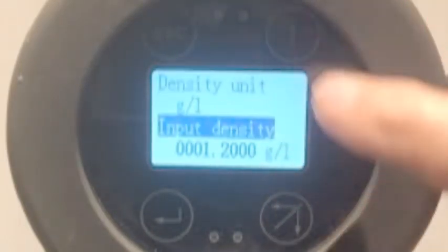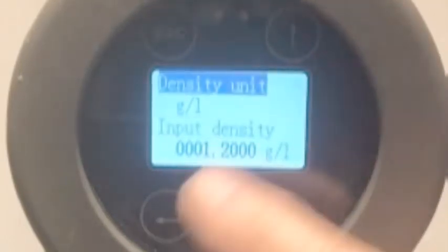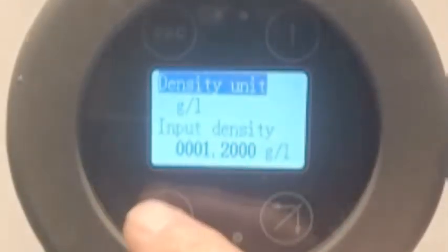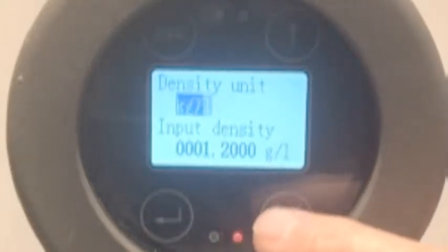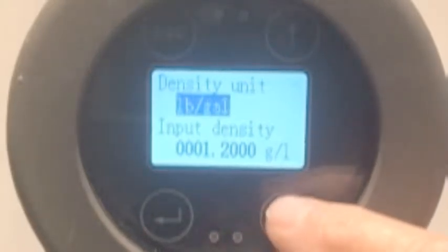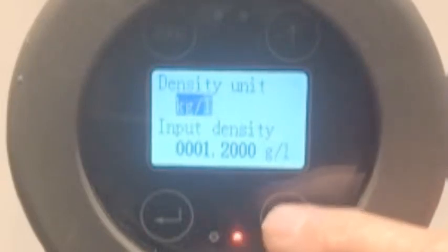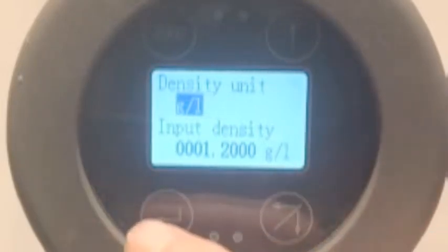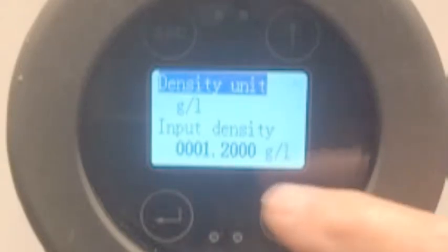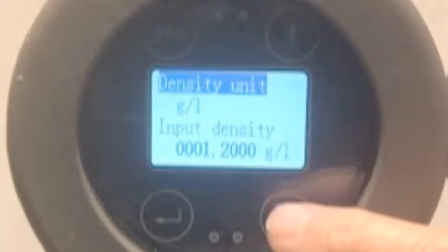The next one is density unit: grams per liter. We can select and change the units if we want. I'll enter and cycle through to see what's available. I'm going to leave it in grams per liter. Enter. And here is the input density: 1.2 grams per liter — that is air.